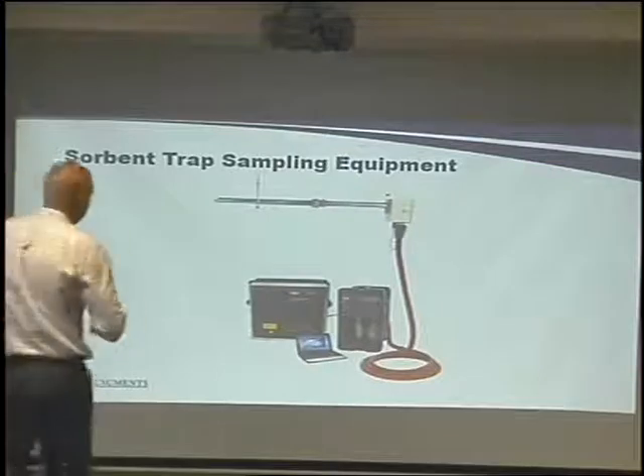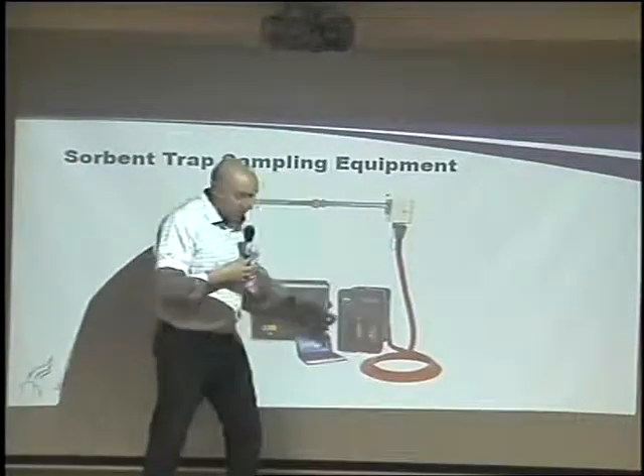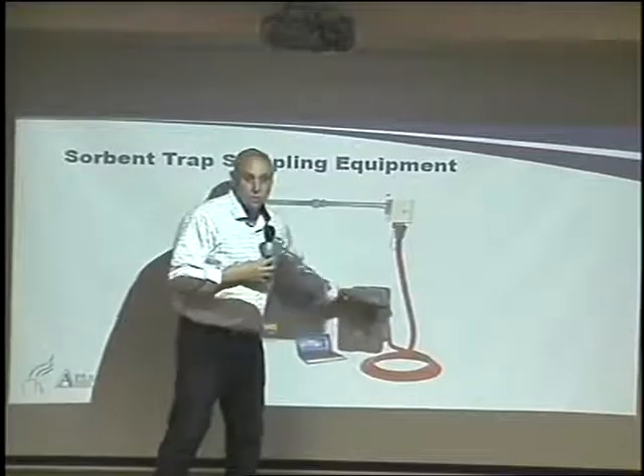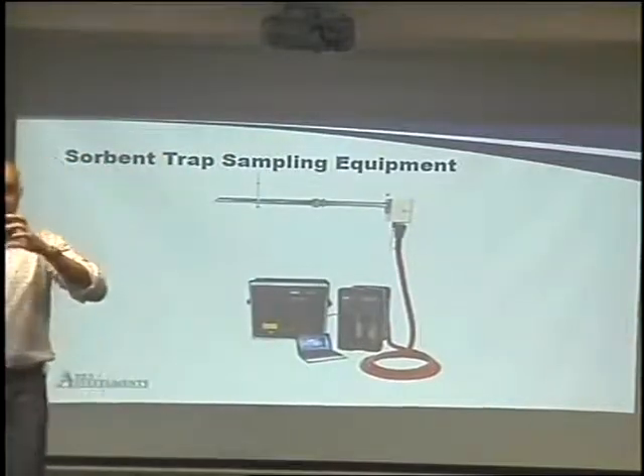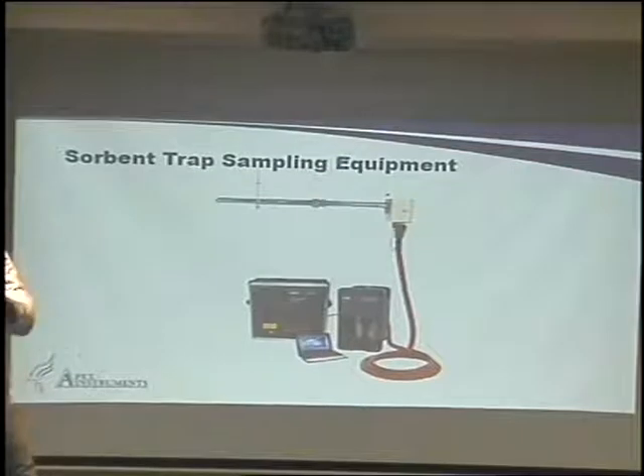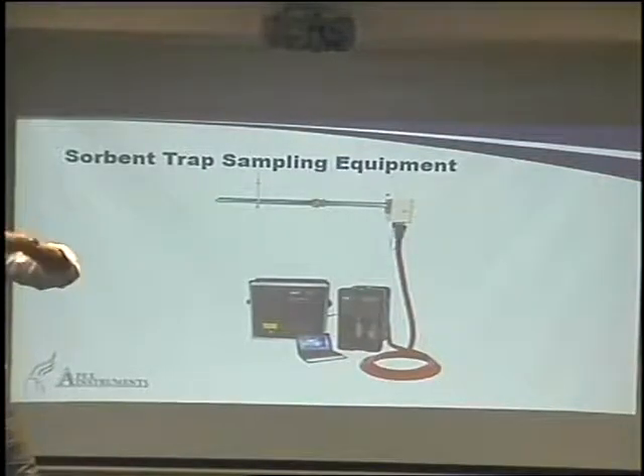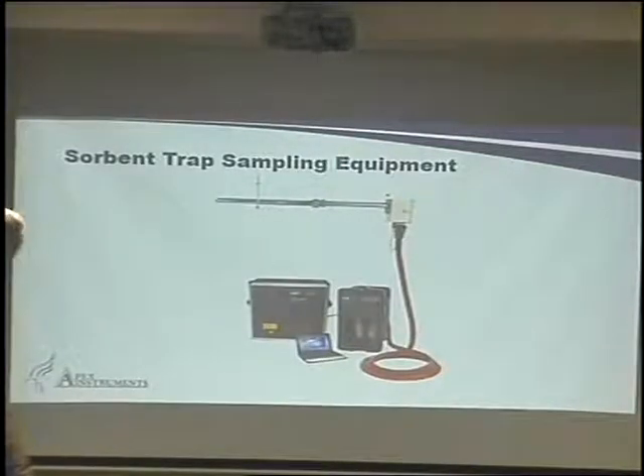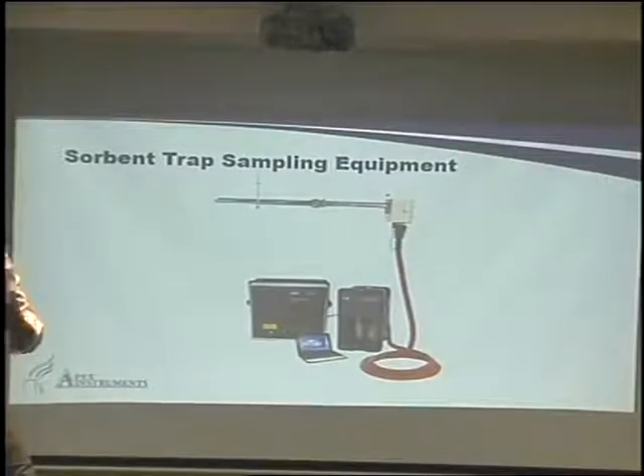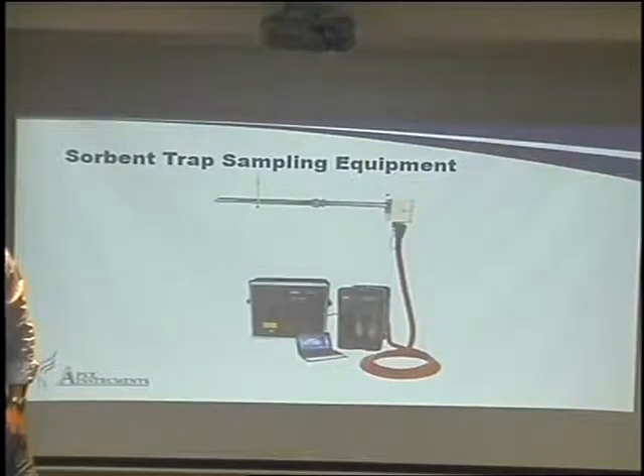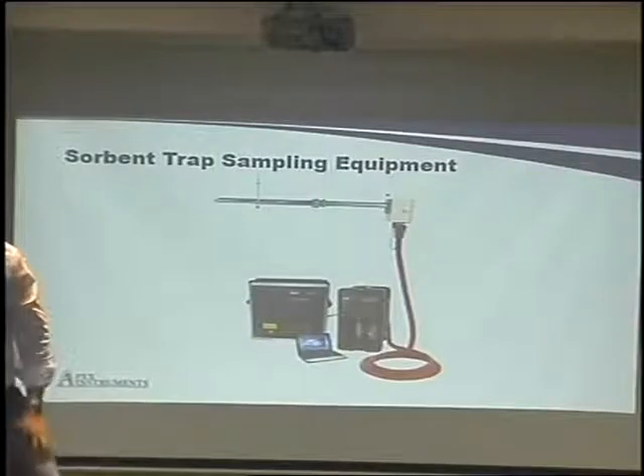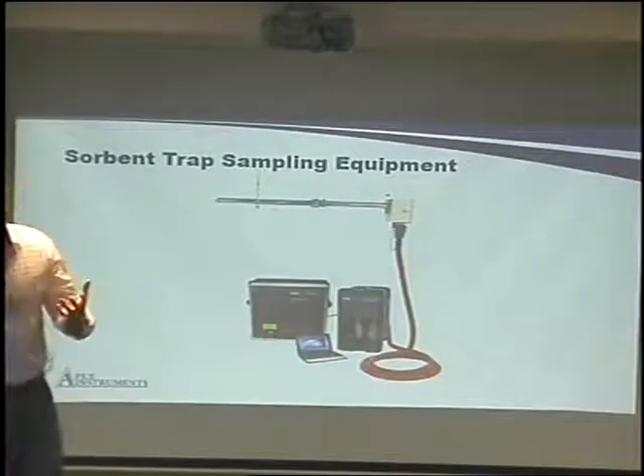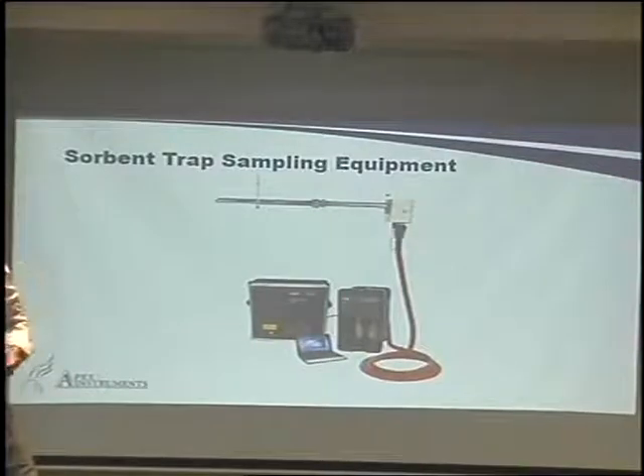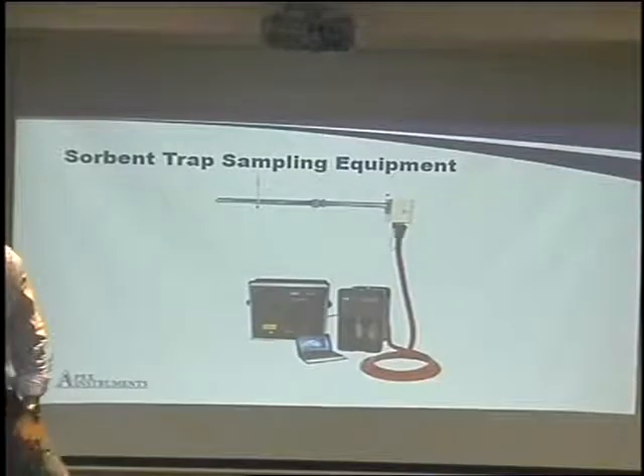So there's unique situations. Again, this is our Stirling cooler. It works. It's got nitrogen inside. It presses and it makes a little coil on the end freeze, makes it cold. Then we run the gas by it to make our sample cold and to drop out the water. The other option, as I said, is passive, silica gel or something like that to remove the moisture and the gases from the sample.